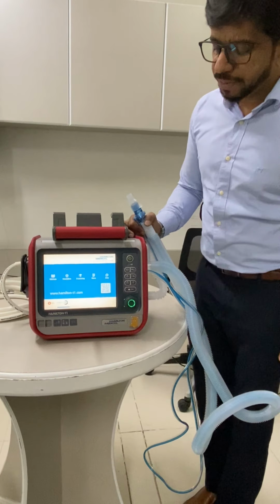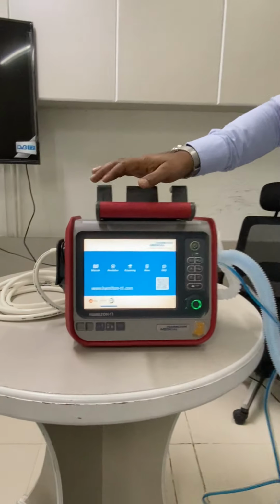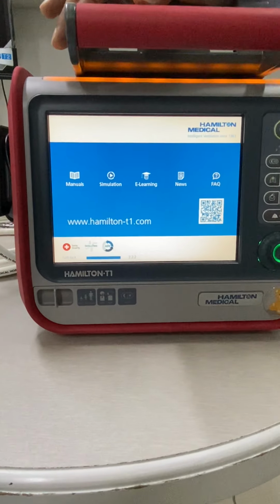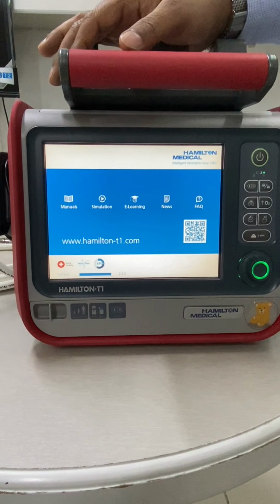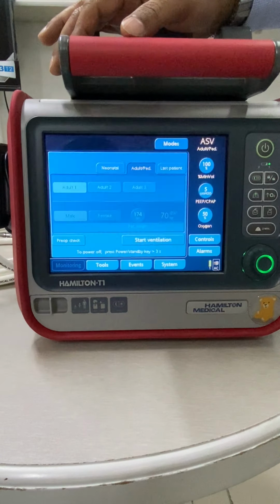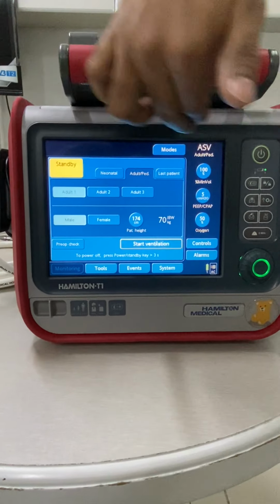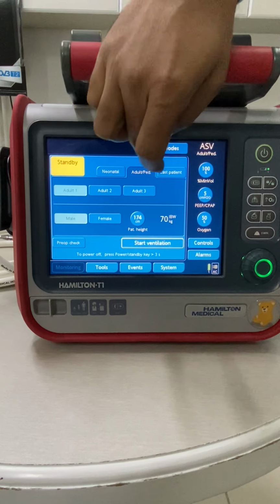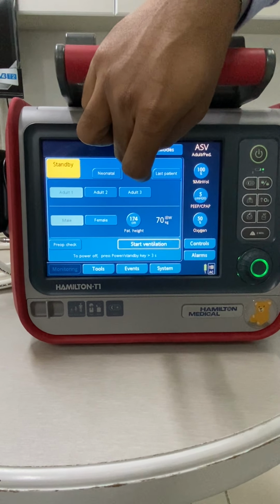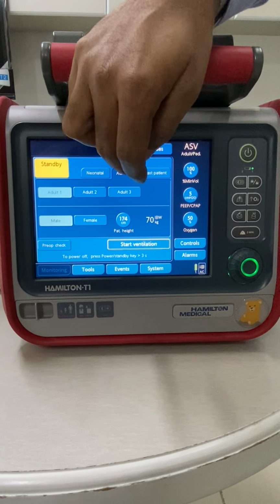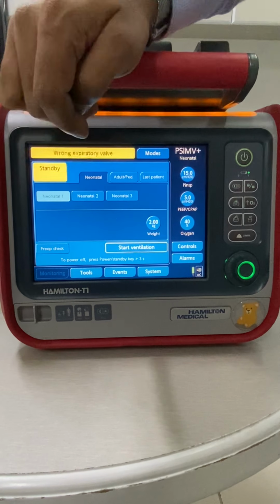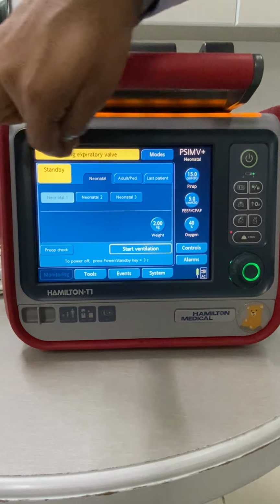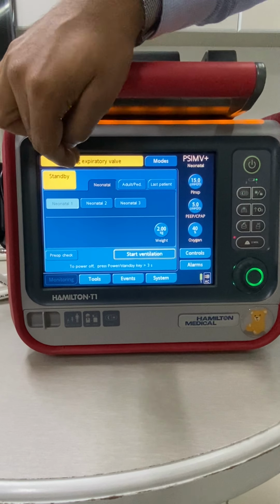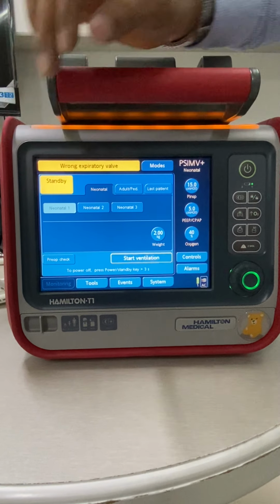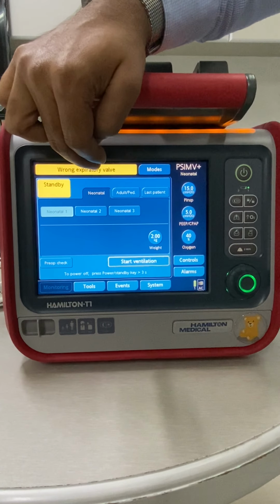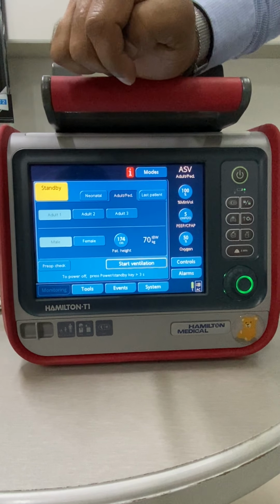So this is the self-test screen. Yes, so this is the standby. When it is on standby, you can see that by default adult pediatric is chosen. If you want to go for neonatal, you have to press neonatal. Then you can see the message, wrong expiratory valve. So if you're going for a neonatal patient, change the expiratory valve as I mentioned before. Otherwise go with adult pediatric.